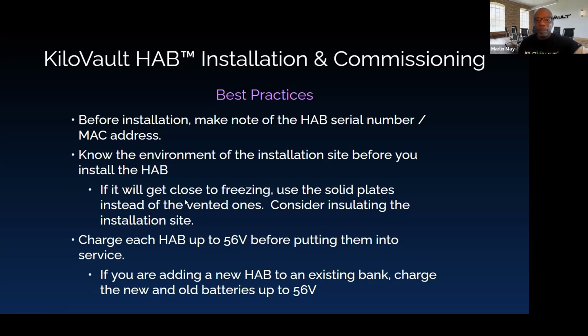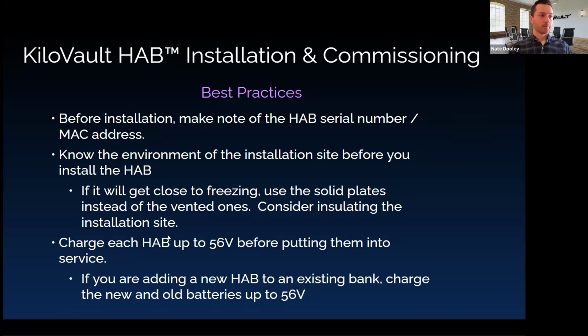Next, please. Note on that too, we often get tech support calls, as I alluded to earlier, about the balancing not working, especially if the voltage difference is really significant. It's just going to take a lot more time and effort for the batteries to balance, so that's why this is a best practice. If I were just listening to this presentation offhand, I might be scratching my head and say, well, I thought they were supposed to balance, so why do I need to do this?